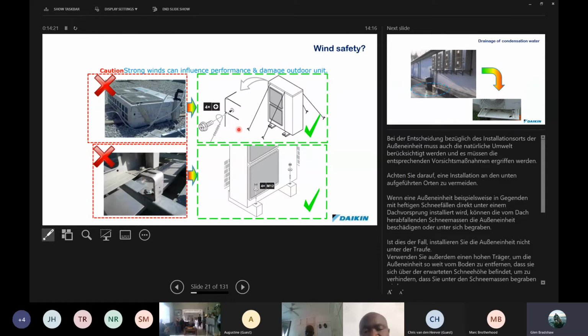Okay, right. Another problem, and this is something that we have on the coast. We have wind. When we place a unit, we need to consider that strong winds can blow units over. I've seen large VRV systems that are close on 300 kgs get blown over in Somerset West, and that caused the damage of compressors. This type of thing over here will cause compressors to become damaged because they'll pump away their oil and then eventually become mechanically damaged. So we need to consider how we're going to strap units down.